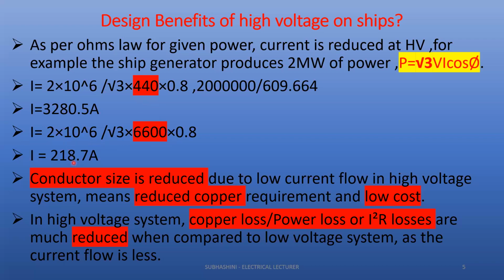Now, the advantage of reduced current is that the conductor size is getting reduced. The current is carried through a cable, so the conductor size is getting reduced. When the size is getting reduced, it means reduced copper requirement. Whatever it is hanging over, whatever switchgear we are using, whatever stainless steel material, whatever the conductor is carried through, everything comes at low cost because the size is getting reduced. So the weight is getting reduced, so the cost is getting reduced. This is the biggest advantage we can say.